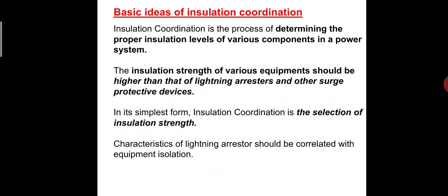Basic ideas of insulation coordination. Insulation coordination is the process of determining the proper insulation levels of various components in a power system. The insulation strength of various equipment should be higher than that of lightning arresters and other surge protective devices.